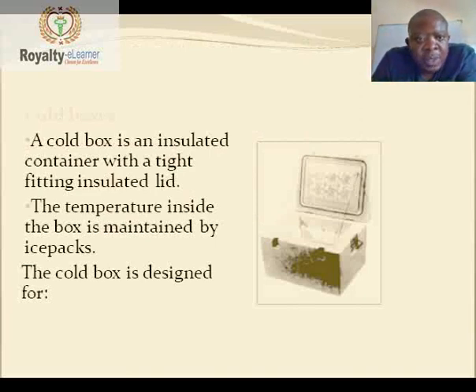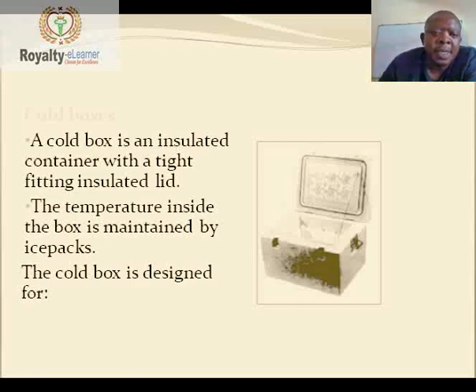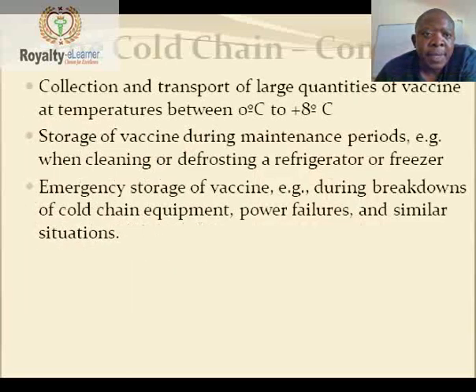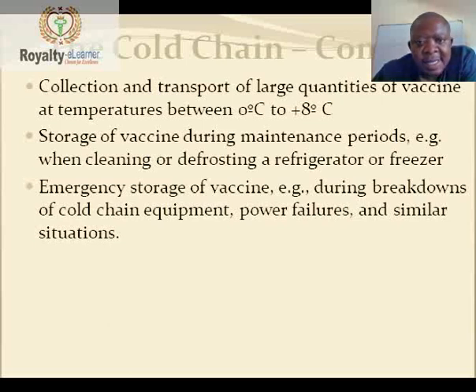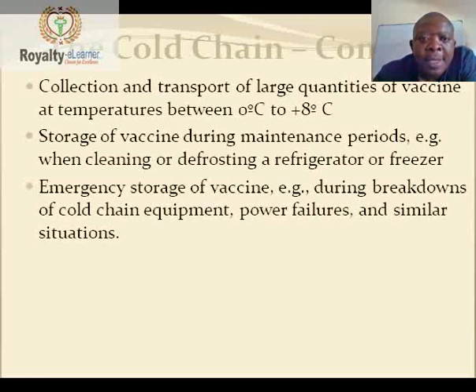Cold boxes are containers with a tight-fitting insulated lid. The temperature inside is maintained by ice packs. Cold boxes are designed for collection and transport of large quantities of vaccines at 0 to positive 8 degrees Celsius, and for storage during maintenance periods such as cleaning or defrosting a fridge or freezer, and for emergency storage during equipment breakdowns — always keeping vaccines between 0 to positive 8 degrees Celsius.